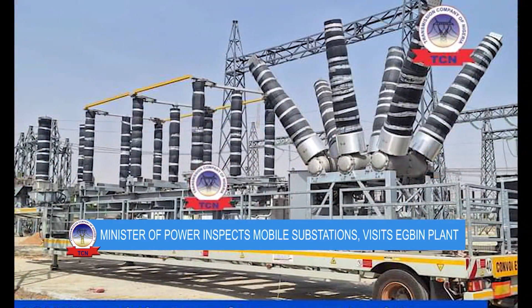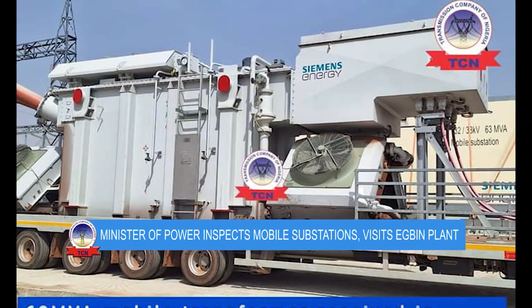Just recently, the Kwanar Dangura 132/33 kV transmission substation of the Transmission Company of Nigeria, TCN, received one of the 63 MVA mobile transformers and its accessories. Upon completion of the installation, which is ongoing, the substation's capacity will increase by 50 megawatts, increasing the available bulk power for Kano and Kaduna electricity distribution companies to offtake for onward delivery to electricity consumers.